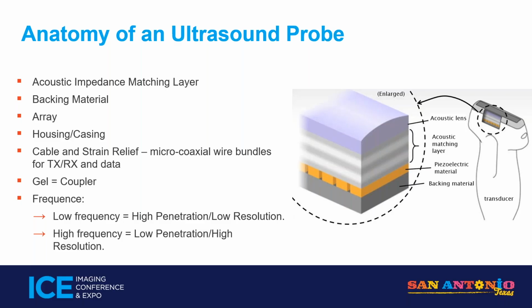Cable and strain relief. Your cables need to be intact, no cuts, no cracks. Strain relief protects the cables inside from damage. So if the strain relief is coming loose or broken off, you need to get that dealt with. Those are repairable things. As soon as it happens, take it out of service and get it repaired. Most companies offer a loaner probe. So if we have a loaner, for example, we'll send you a loaner to put in service while yours is being evaluated. Okay.